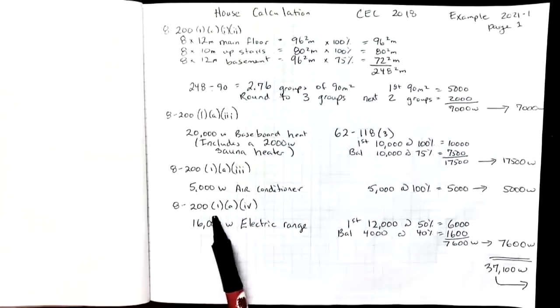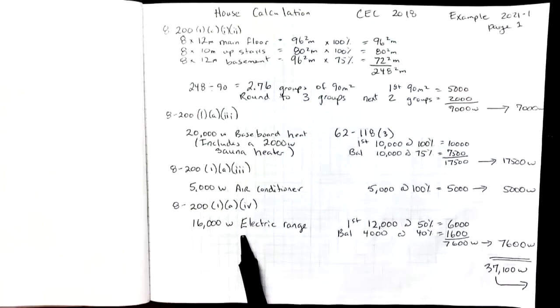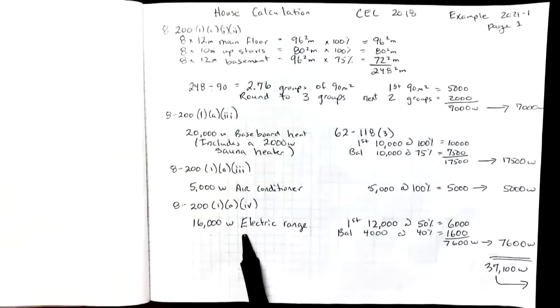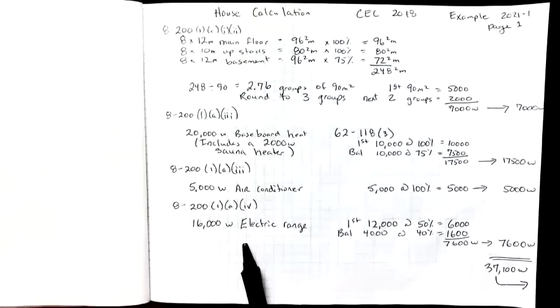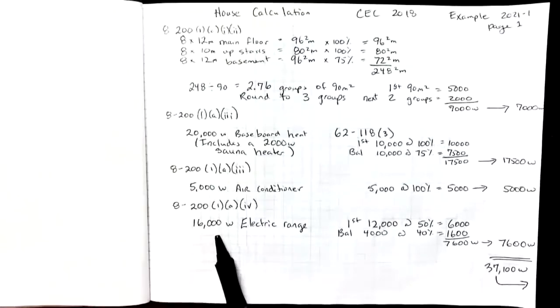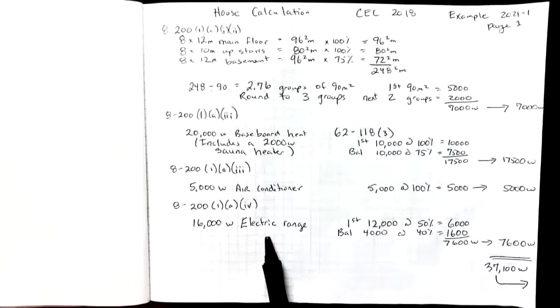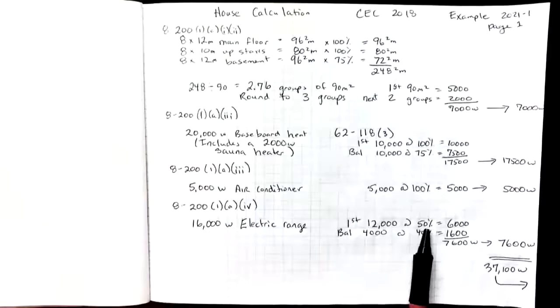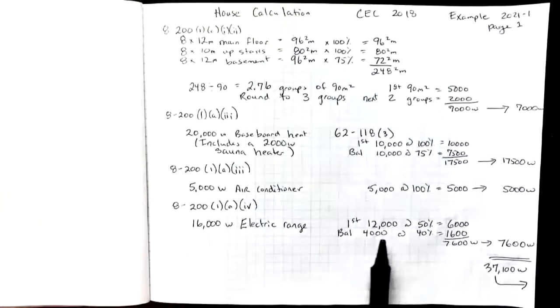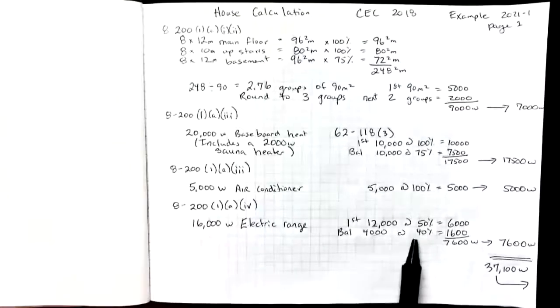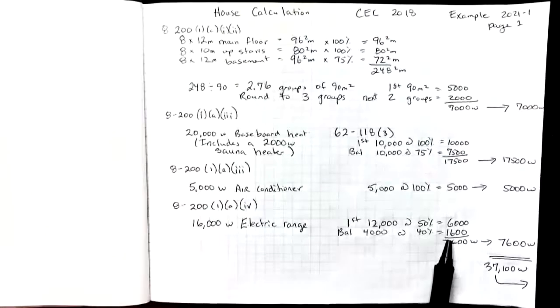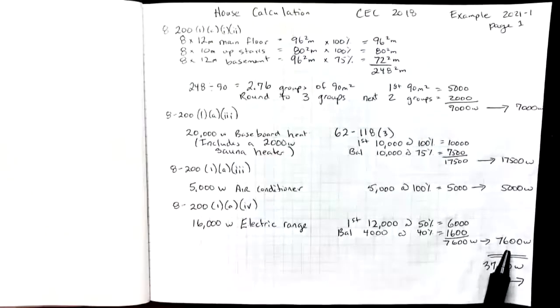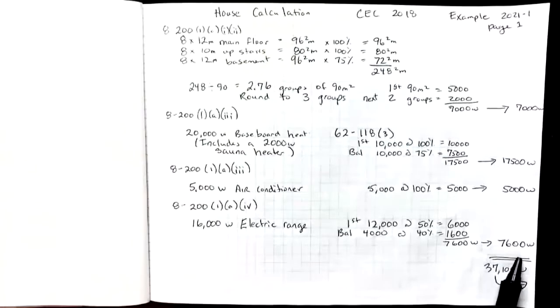Rule 8-200(1)(a)(iv) speaks to what we do for an electric range. Remember this is the demand factor towards the main service. There's a different rule for the actual branch circuit calculation. In this case I have a 16,000 watt electric range. The rule tells me to take the first 12,000 at 50% which is 6,000 and the balance at 40%. We have 4,000 left over. Gives me an additional 1,600. So it takes 7,600 watts towards the main service.